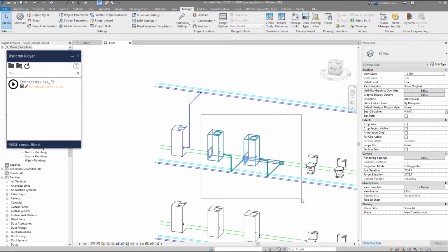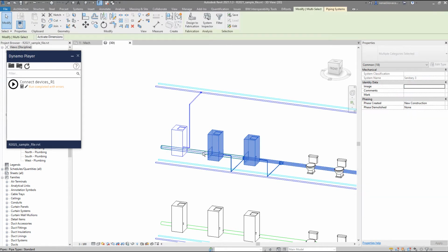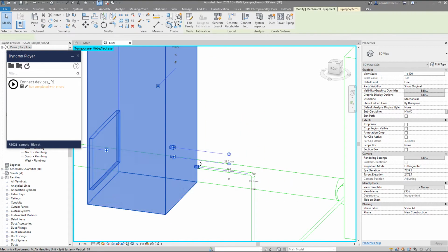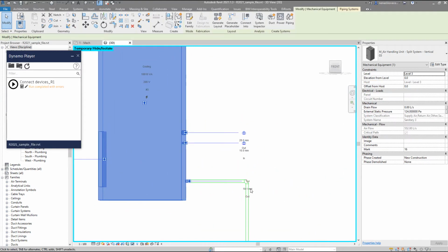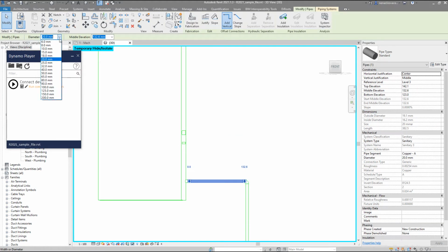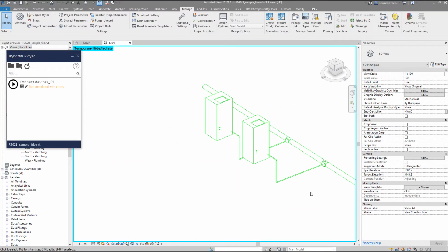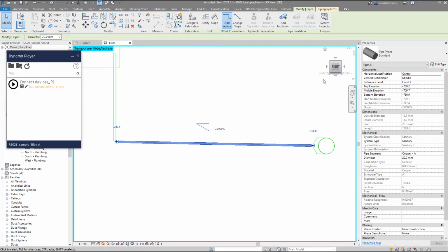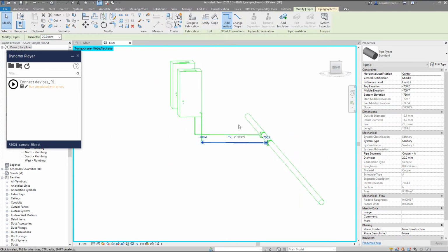Okay, I will isolate this. So did we connect with the sanitary? Yes, we did. What is the diameter? 19. The used diameter is 20 because 19 is not defined for our pipe class. And now, did we include that slope? Yes, we did, and it's 2% of slope for each pipe.